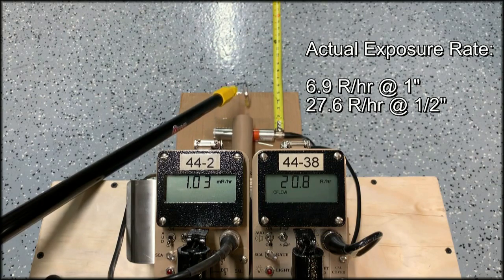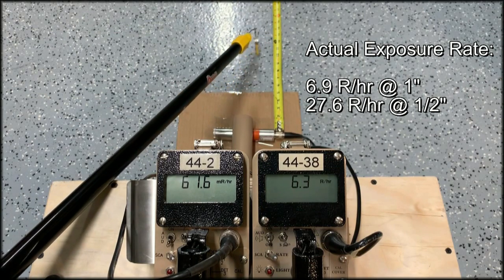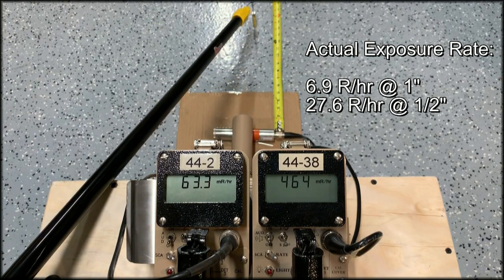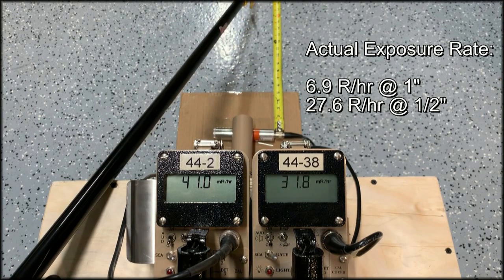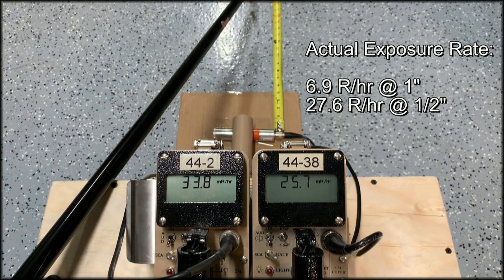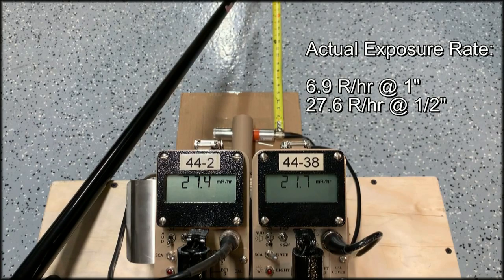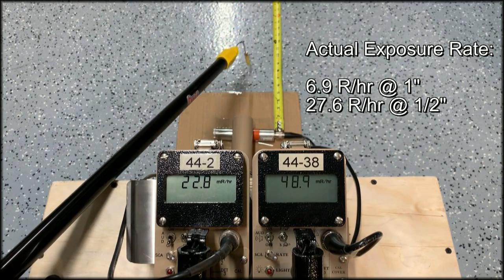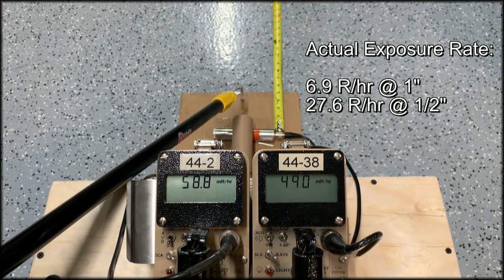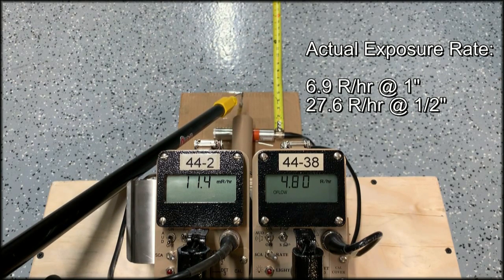And the actual dose rate's going to be different because similar to the 44-2, the 44-38 also has an upper limit. And with dead time correction, that's about 500 mR per hour. So it's really only under reporting what the actual dose rate is as well.